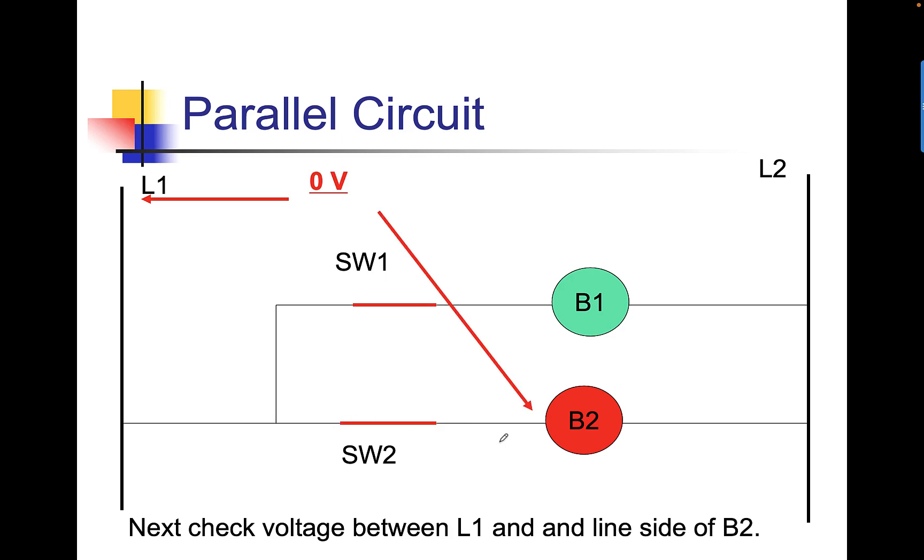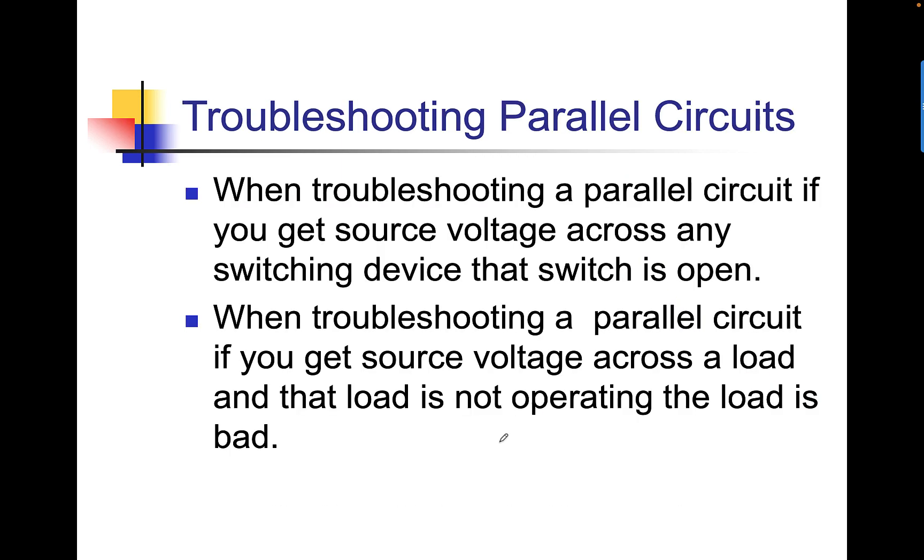Now, is this bulb good or bad? Well, from the PowerPoint diagram, I can't tell you, but if the load is operational, in other words, if whatever B2 is working and I have 240 volts, the bulb is good. And it's a good reason. If I have 240 volts at this point and the B2 is not doing what it's supposed to do, let's just say it's a light bulb, the light bulb isn't on, it tells me we have a bad light bulb. And I'm going to continue.